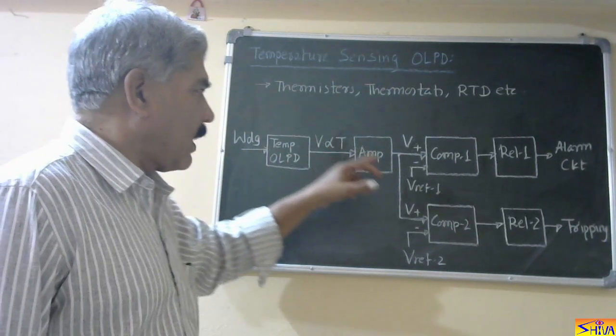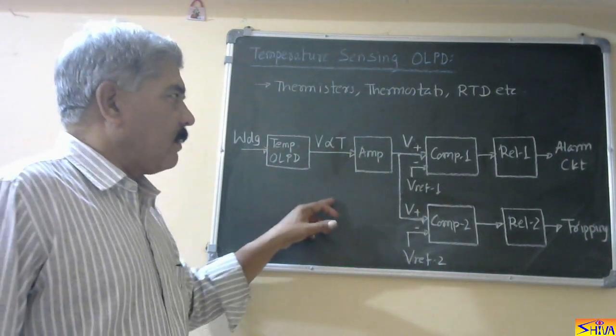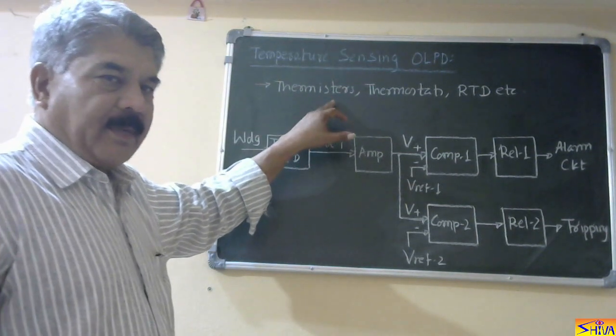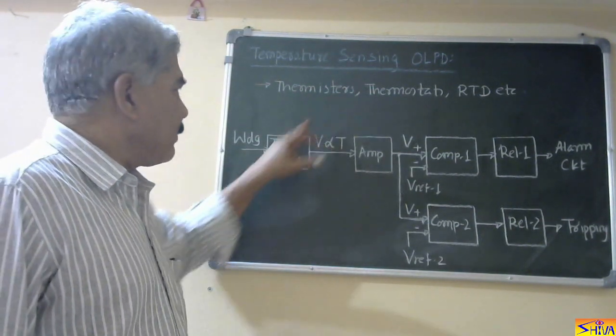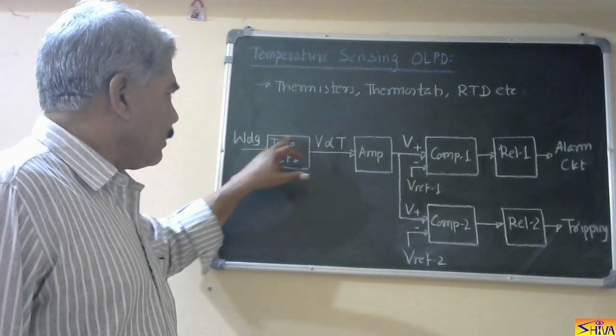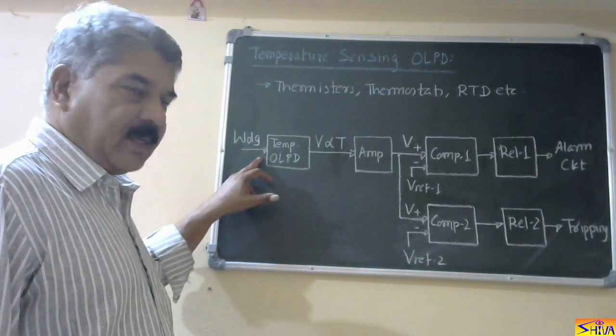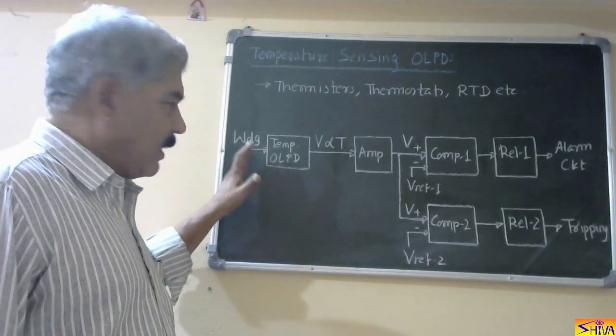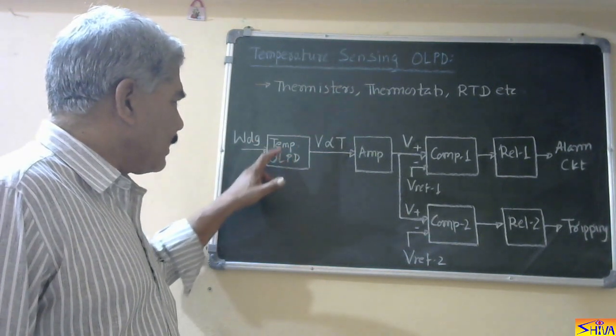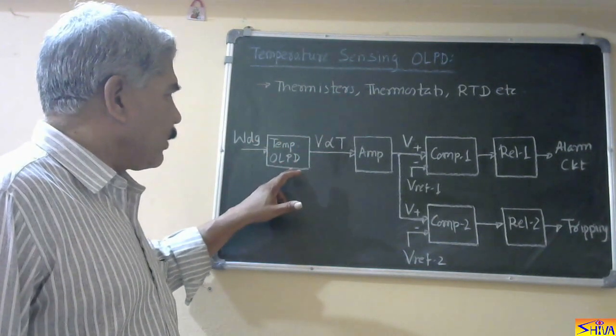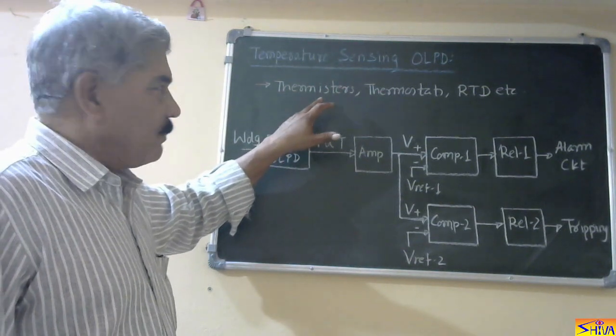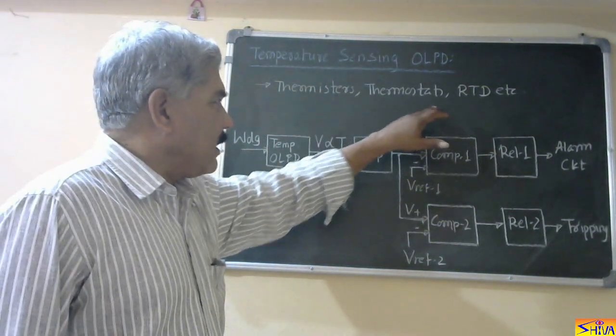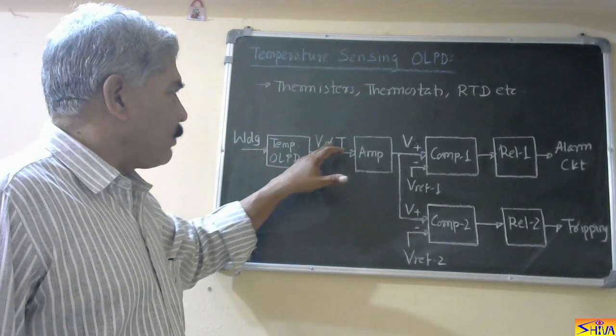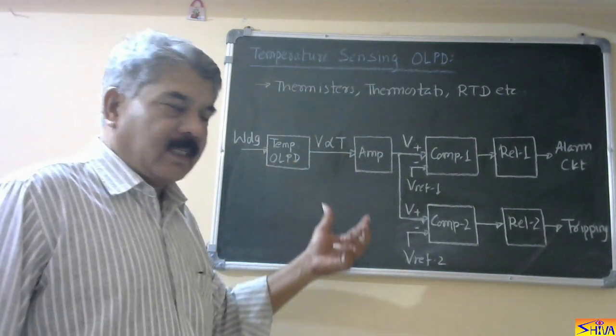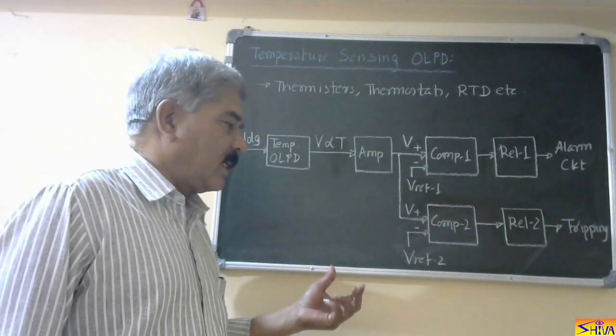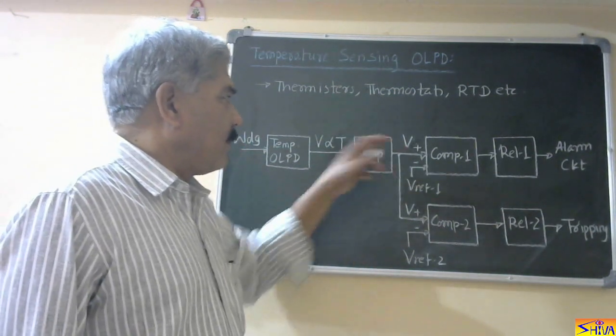So here is the block diagram for the operation of this temperature sensing overload protective device. They are embedded in the machine and they are placed over the winding. So from winding they detect the temperature. So it is temperature sensing overload protective device. It can be thermistor, thermostat, or RTD. They produce voltage proportional to temperature. This voltage is small, so we need to amplify this voltage. So here we get amplified voltage.